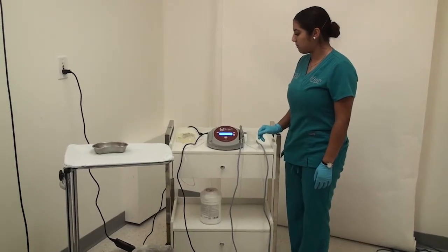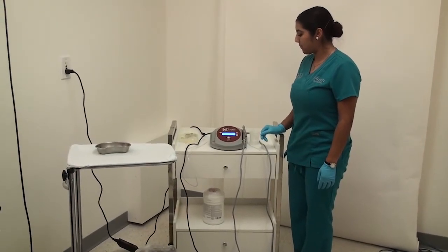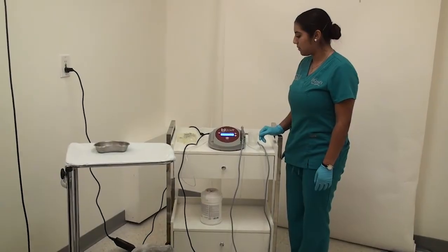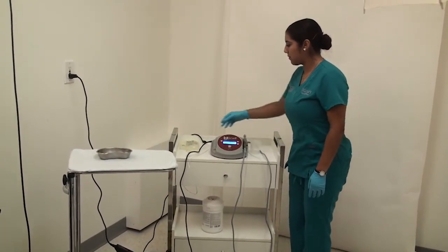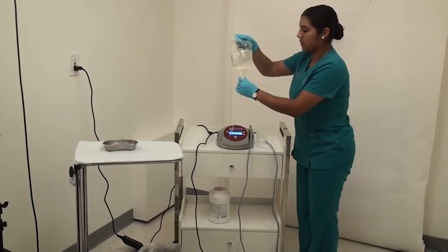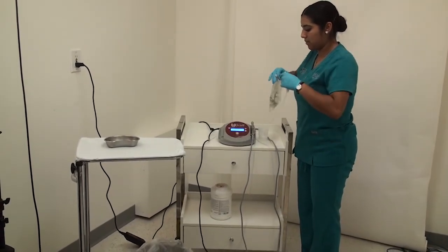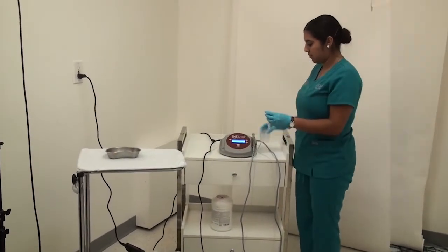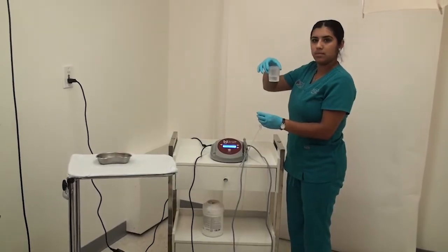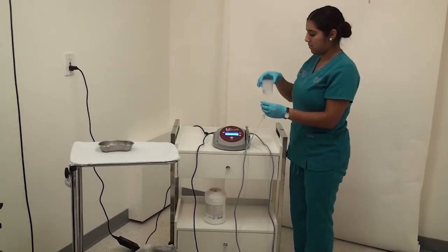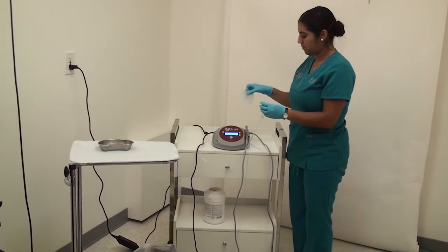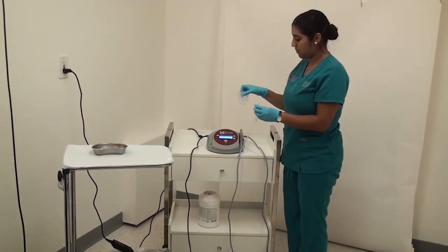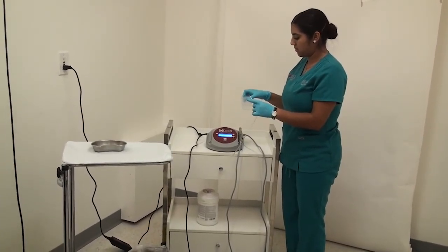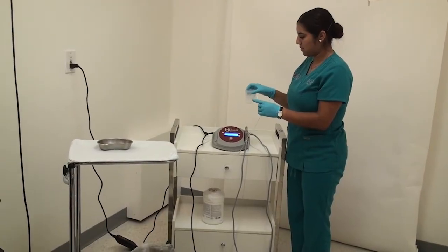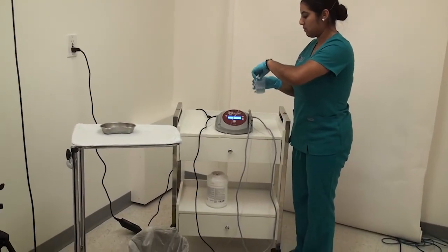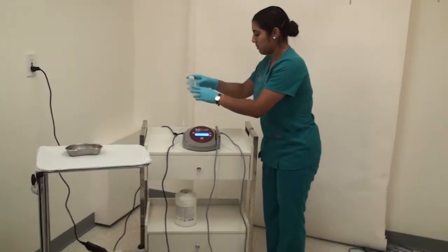Now it is time to break down the equipment and set it up for sterilization and cleaning. The first thing to do is disconnect the fluid bag. Dispose of it. Next, you will have connected the tubing port to about 2 ounces of distilled water. This would be used to flush the handpiece. You will want to flush the handpiece and free it from any residue or debris as well as salt water. You place the bag end of the tube into the cup of distilled water as shown.